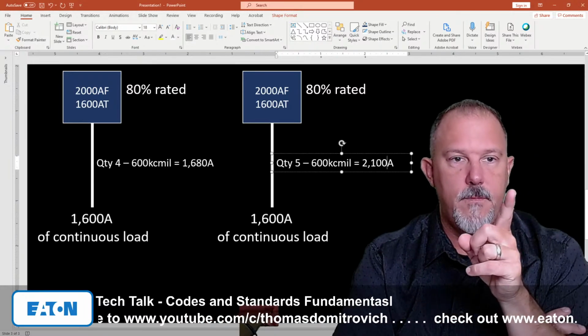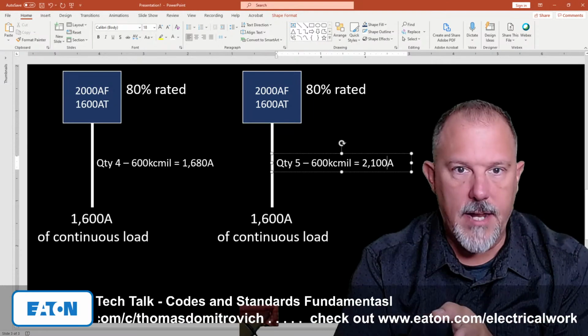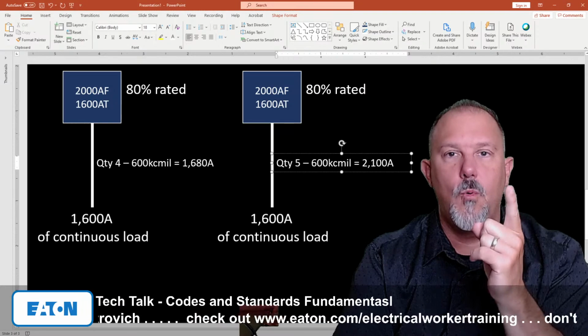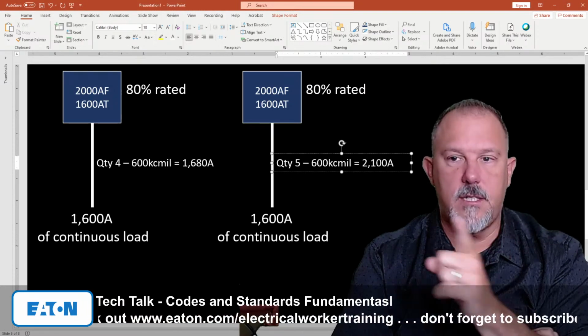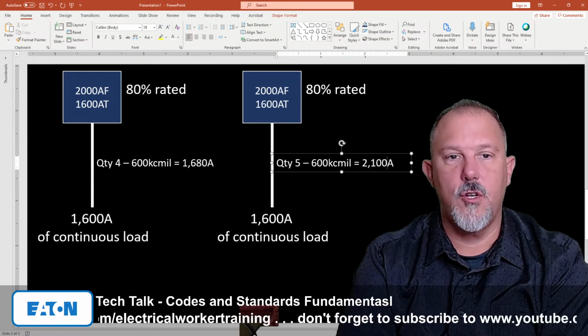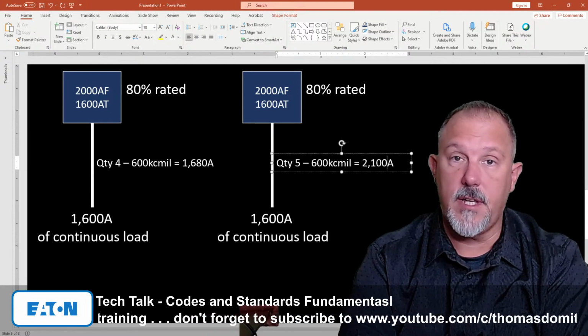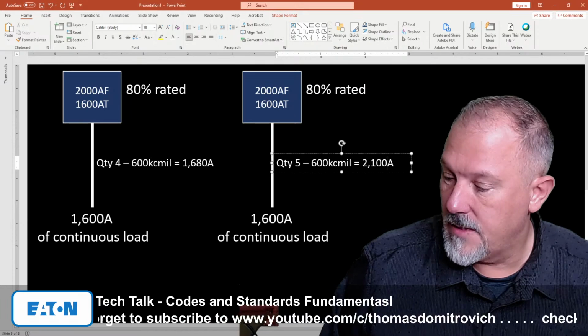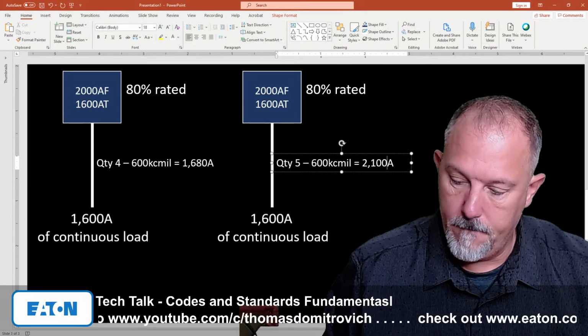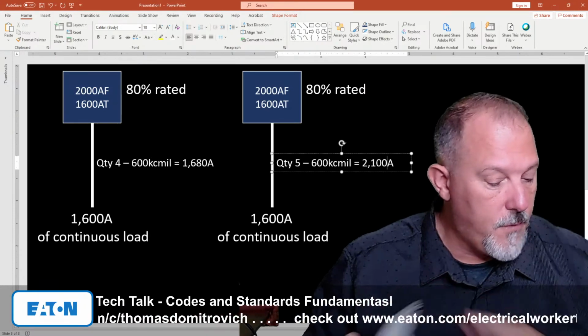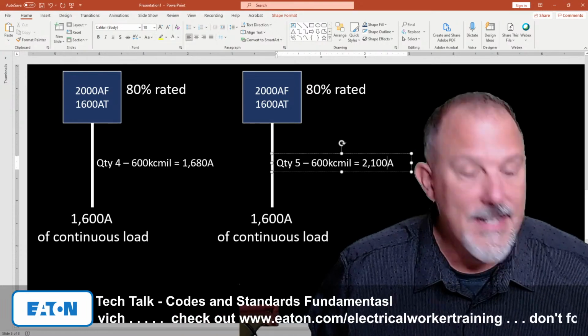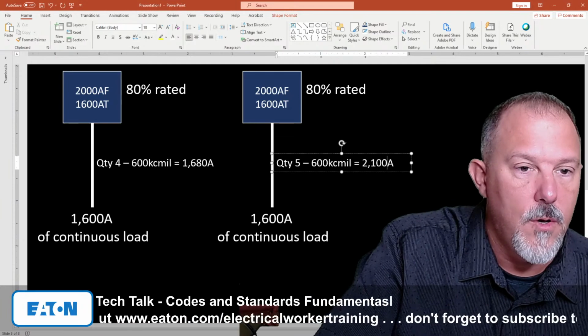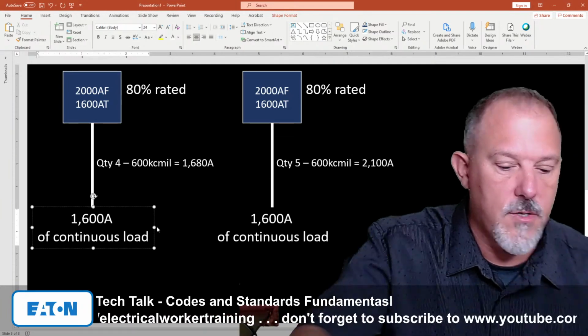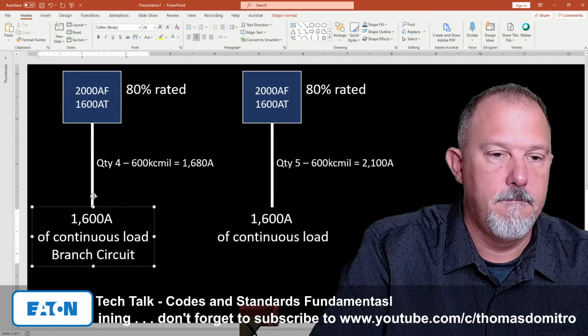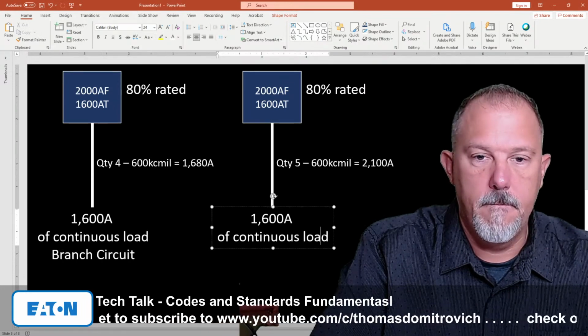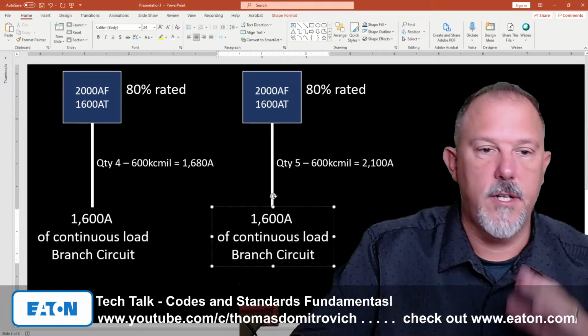Which one of these is the right application? 80% rated breaker upstream in both cases, 2,000 amp frame breaker, 1,600 amp trip, 1,600 amps worth of continuous load. Which one is the correct installation? Is it quantity 4, 600 kcmil, or quantity 5, 600 kcmil? Now, before I answer that question, I am going to take you to 240.6. What does 240.6 say? First of all, this is a branch circuit. Both of these are a branch circuit.